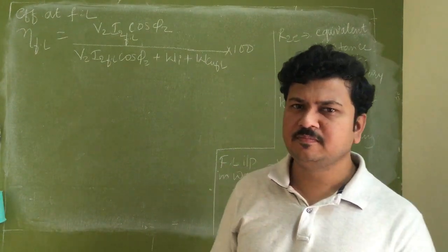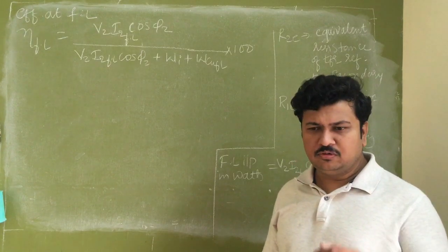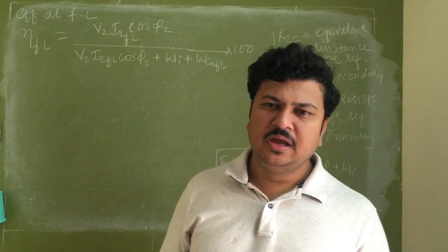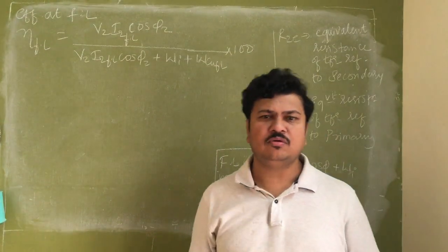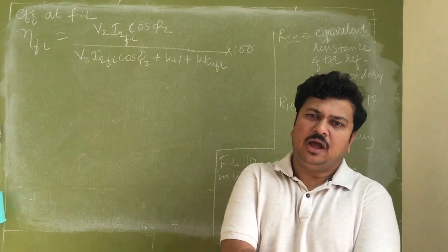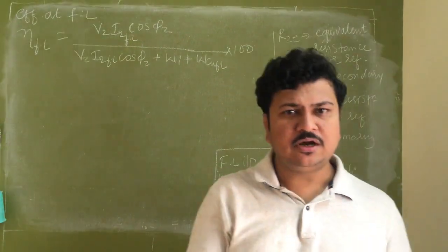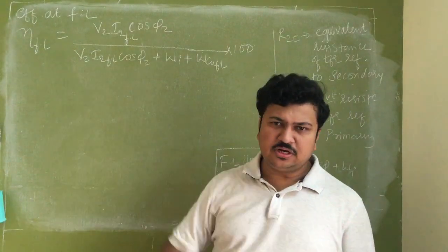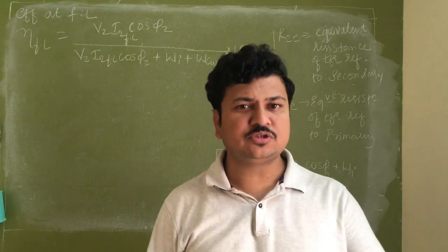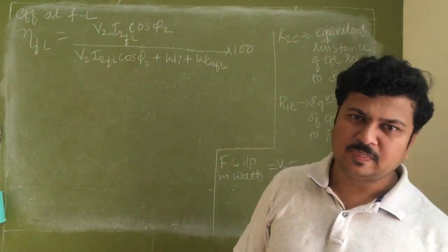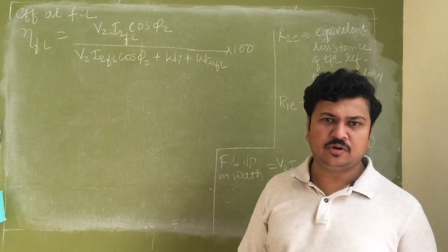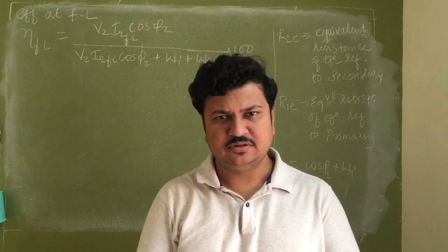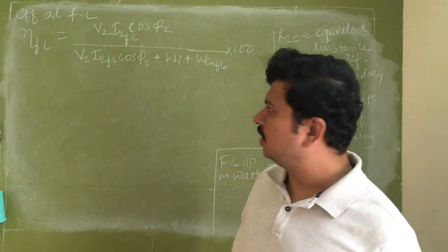Say for example, now if I have to install a transformer in my premises to get the power distributed, I will not install a transformer of 200 kilovolt amperes or 200 kVA. I will be installing say around 300 to 350 kVA transformer. Why? Because once I install the transformer, I expect it to operate for years together, not even months. Because transformer is operating 24/7/365. There is no rest for the operation of transformer.